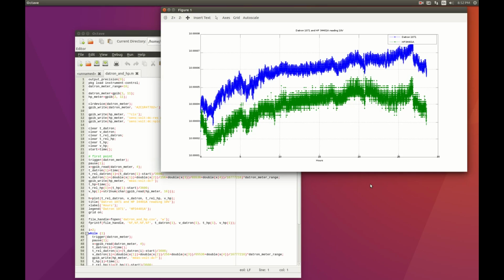I let this run a little longer, so now we have about 28 hours of data, and the meters seem to have drifted apart a little bit more. Now they are running about 2.5 ppm apart, which I believe still looks quite good. Even if we assume that the Hewlett-Packard meter is perfect, this means that the Datron meter drifted up about 1 ppm in 28 hours, which is well within specs. Here are the specs for the Datron 1071: DC voltage accuracy, 24 hours at 23 degrees C plus or minus 1 degree, 10 volt range, 3 ppm of reading plus 2 digits, 90 days 15 ppm, and 1 year 20 ppm.